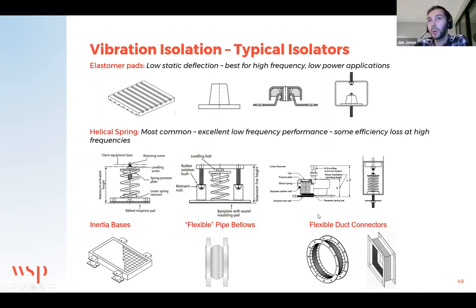A few extra points. Flexible pipe bellows, flexible in inverted commas there. They are flexible and they are there to help deal with displacement between pipework and pumps, for example. But in terms of acoustics, certainly under high pressures, the fluid within the system can transfer vibrations as if it was a solid, essentially. So whilst these do help with any alignments in the system and any movement in that respect, vibration can still get passed straight through these systems, which is why a certain amount of pipework would often need to be hung on spring hangers or neoprene hangers as well.